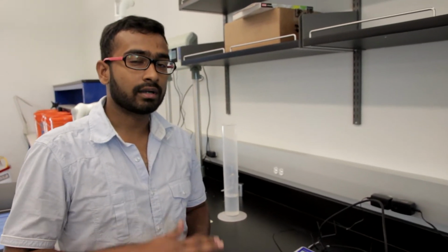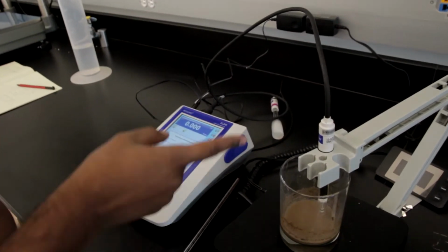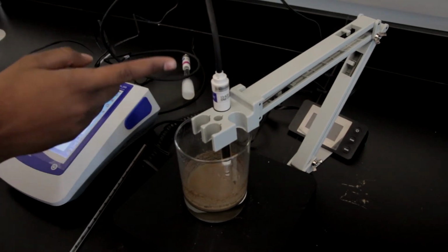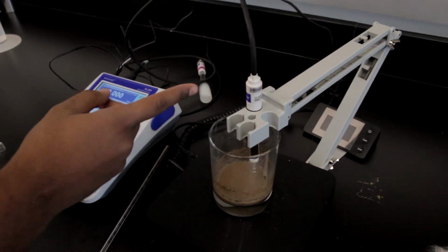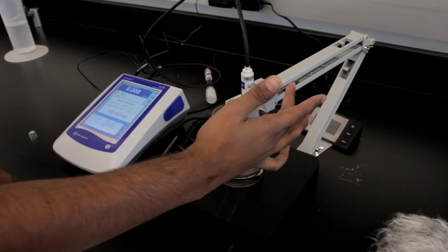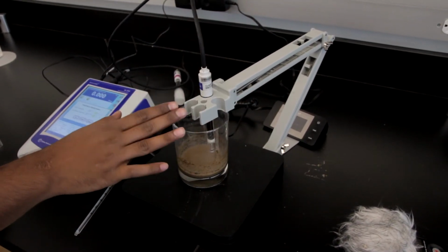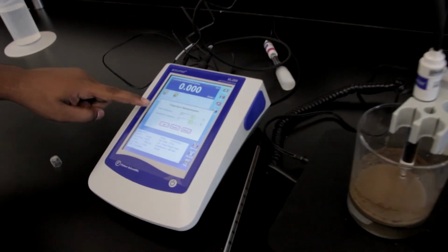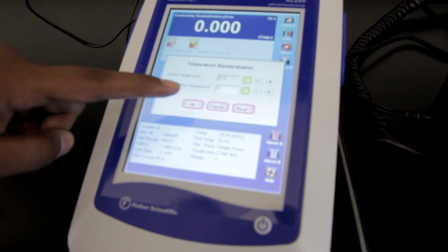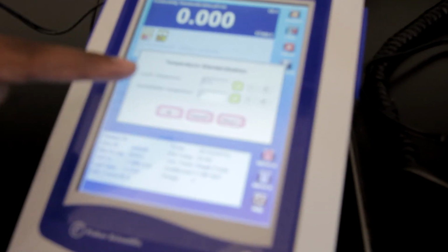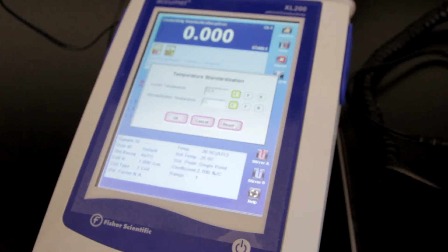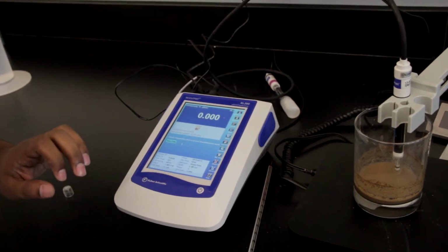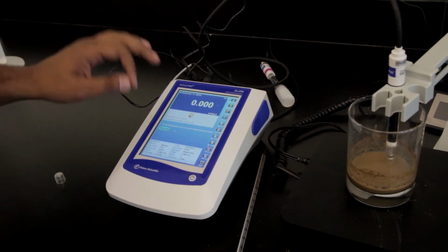Now that we've waited for an hour, our next step, step 3, is standardizing the temperature of the soil slurry solution. What we have here is the Acumet temperature probe. It's an automatic temperature sensor. We have used a stand to hold it for 30 seconds. As you can see, the current temperature is 21.8, and the standardization temperature is 21, which is the temperature of the slurry solution. As we give OK, it's going to standardize the temperature and give us a stable value.